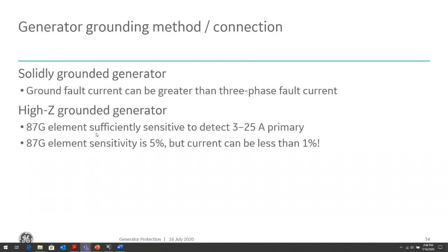The 87G element is one way of protecting for ground faults. It can be set very sensitive, just like the phase fault current. It's the ground differential protection. It operates on the differential principle: current in equals current out, but it suffers the same situation as a ground overcurrent element would. For faults close to the neutral of the transformer, you're going to have very, very low ground fault contribution, and your generator's ground differential might not be able to see that and might not be able to operate.